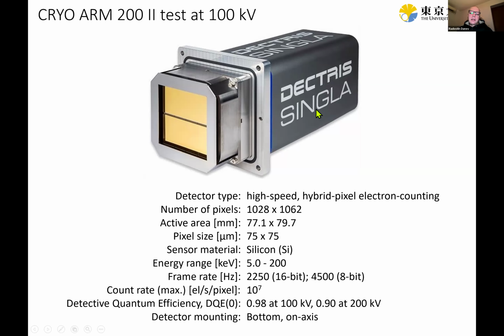So for this, I contacted Dectris, and they were kind enough to loan us their Dectris Singla camera, which you see here. It's a high-speed hybrid pixel detector. That means that each pixel has its own counter. So when an electron hits the pixel, the pixel itself is doing the counting, and this can provide very, very high counting speeds, as you can see here, 10 to the 7 electrons per second per pixel.